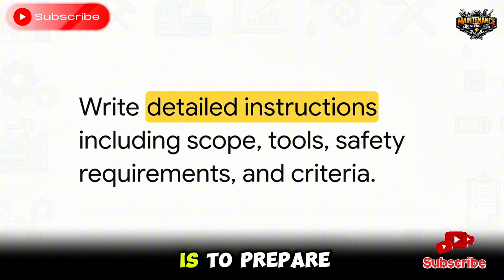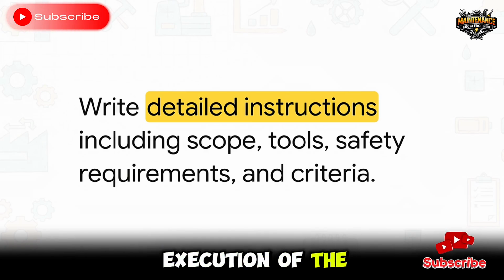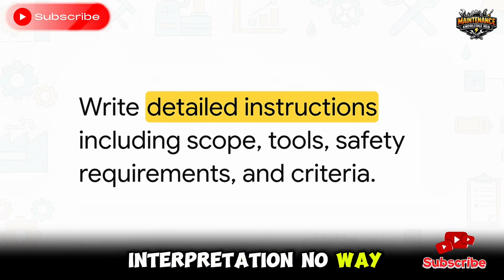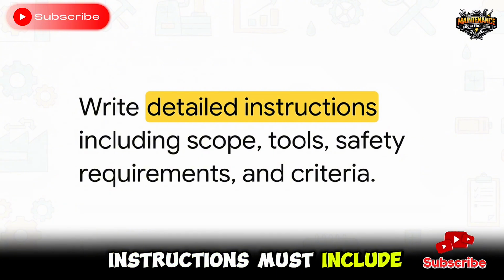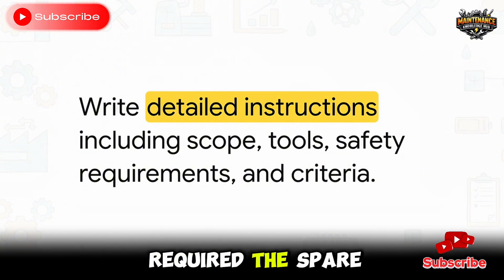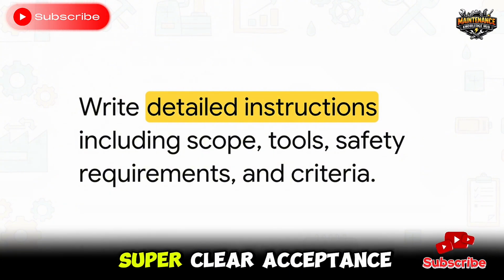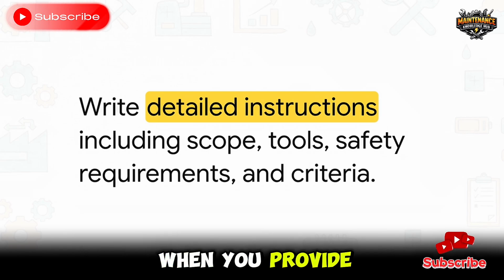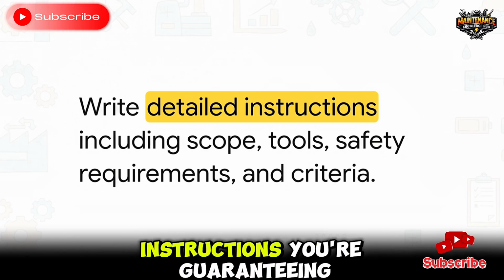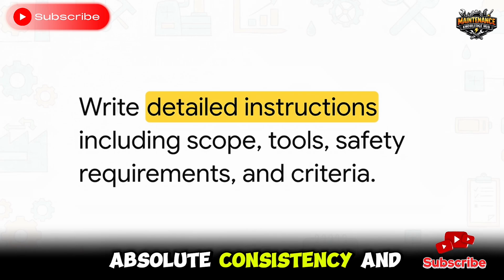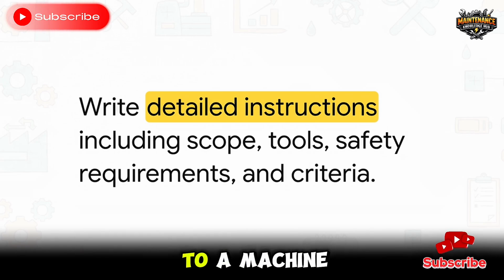Okay, Step 7 is to prepare job procedures. So the absolute crucial point here is this. You cannot leave the actual execution of the work up to interpretation. No way. Your detailed work instructions must include the scope, the exact tools required, the spare parts, safety gear, and super clear acceptance criteria. When you provide your technicians with explicit written instructions, you're guaranteeing absolute consistency and quality every single time they walk up to a machine.